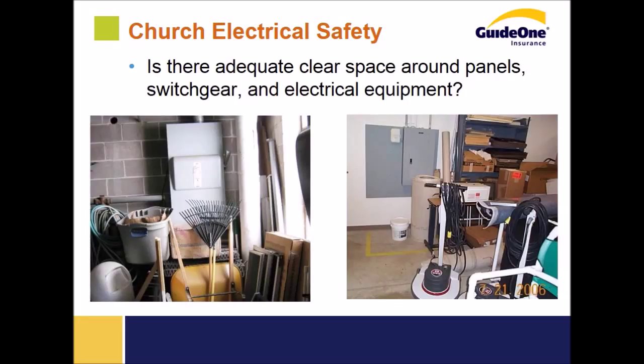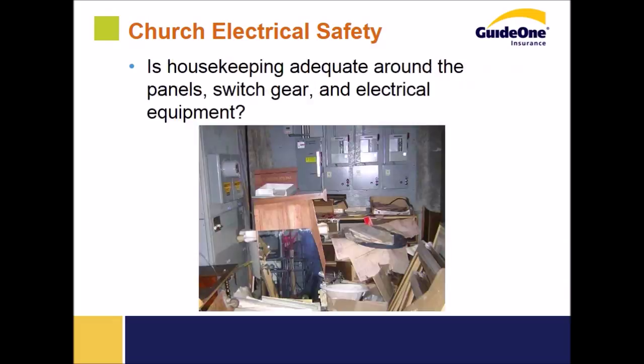The most common recommendation that we see, both from you and from our own people, is to clear space and combustible materials located too close to service panels and distribution panels. There are a couple of obvious reasons for this. First, emergency access in case they need to throw a switch or turn off a breaker. And secondly, to provide proper circulation around the equipment for proper cooling. Yet another reason to keep a 36-inch clear space around this switchgear is to prevent a fire in the case of an arc flash. If you provide that clear space, it's much less likely that an arc flash or a spark from this equipment will start a fire.